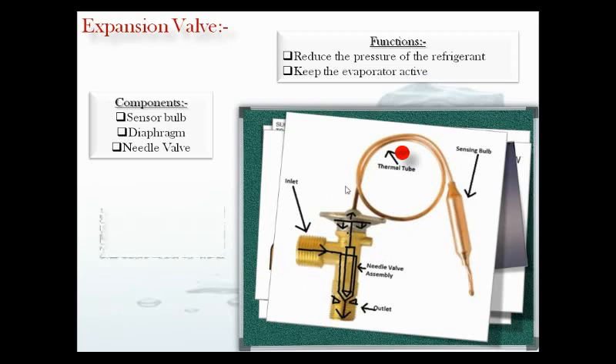There are basically two main types of thermal expansion valve: internally equalized and externally equalized. The difference between them is how the evaporator pressure affects the position of the needle. In an internally equalized valve, the evaporator pressure acting against the diaphragm is the pressure at the inlet of the evaporator. Whereas in an externally equalized valve, the evaporator pressure against the diaphragm is the pressure at the outlet of the evaporator.